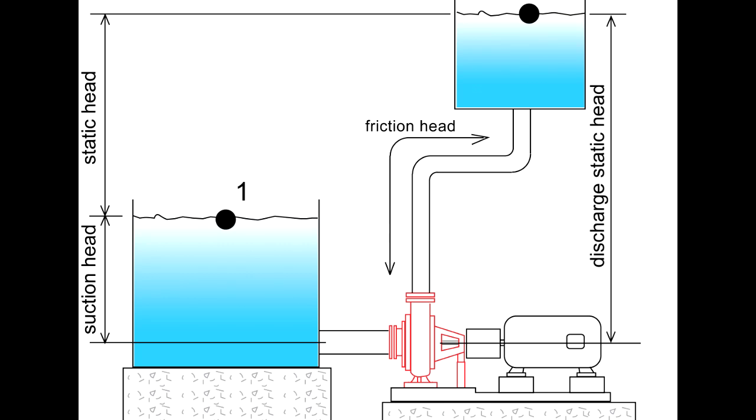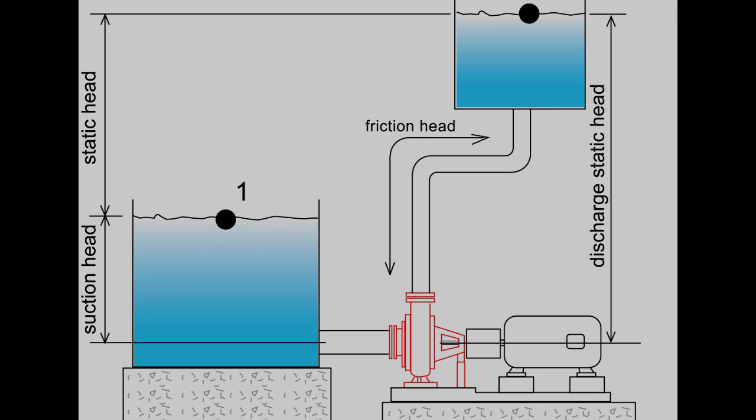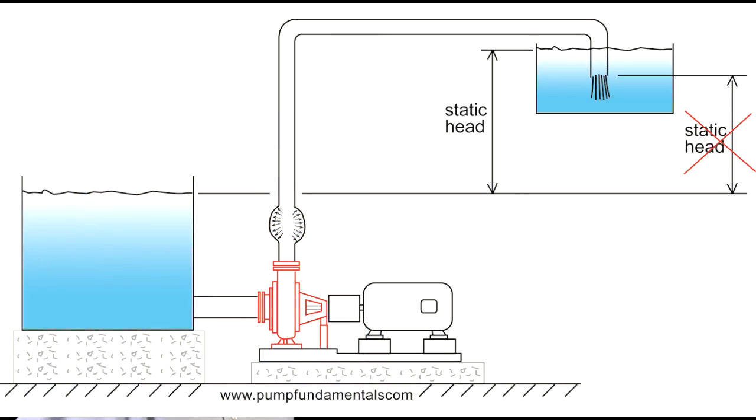If the pipe end is submerged at the discharge side, we take the head between two liquid surfaces and not to the end of the pipe, because we've got to follow liquid from one end to the other. All those fluid particles have to get from the top of the suction tank to the top of the discharge.